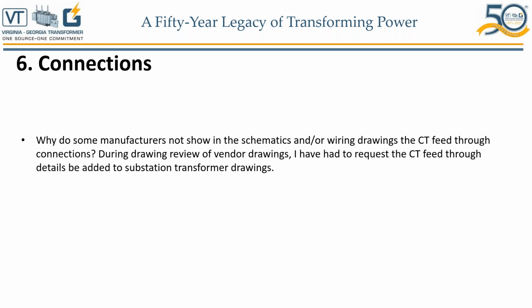That may be the reason. I cannot speak for others, but I have to use my best judgment to answer the question. That may be the reason, because you don't need to do anything in the feed through. However, I do understand why the submitter of this question would like to have the CT feed through connection diagram also, because nobody's perfect. Everybody may make mistakes. What if you receive the transformer and you're testing the CTs and you find out that the CTs aren't really wired correctly per the diagram, the drawing, and you want to troubleshoot it? One of the first things you want to check is that the wire running from the CT feed through, say from the top of the tank, to the control cabinet is not swapped accidentally. That's probably why it is important for you to have that CT feed through connection on the drawing.